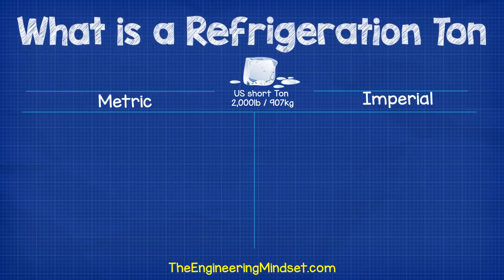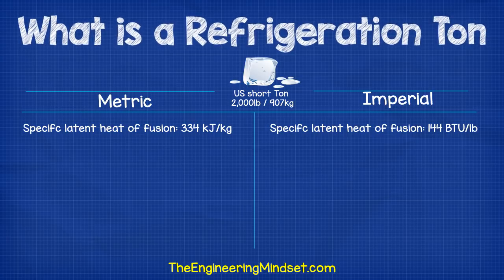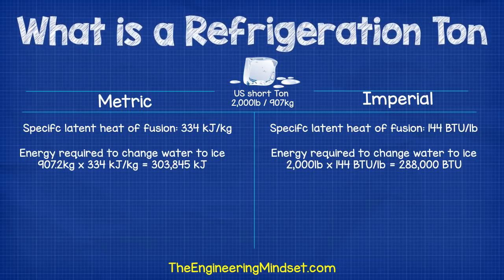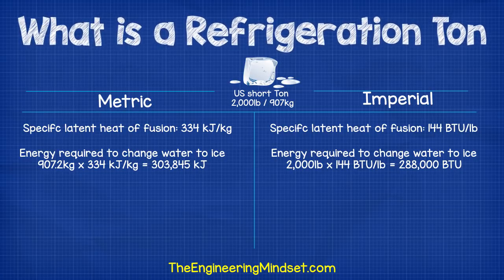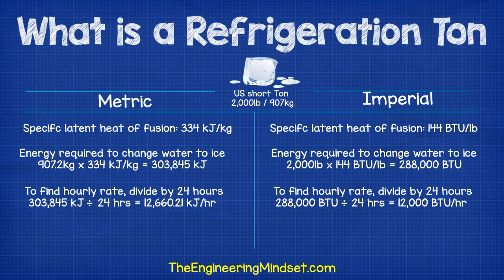A short ton is equal to 907 kilograms or 2,000 pounds. The latent heat of fusion for ice is 334 kilojoules per kilogram or 144 BTUs per pound. To calculate the latent heat cooling load, just multiply the respective units together. To convert this weight of water into ice within 24 hours, on the metric side you need to extract 303,845 kilojoules, or in BTUs 288,000. To find the hourly rate of cooling, divide by 24 hours. On the metric side: 303,845 kilojoules divided by 24 hours equals 12,660.21 kilojoules per hour. On the imperial side: 288,000 BTUs divided by 24 hours gives us 12,000 BTUs per hour.